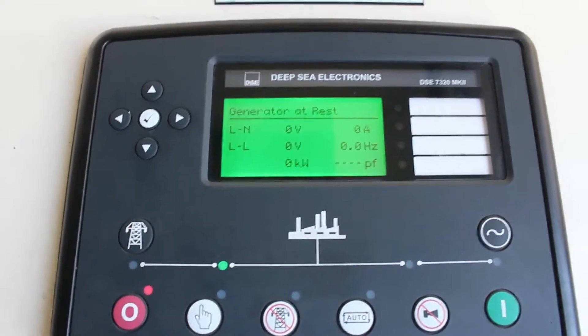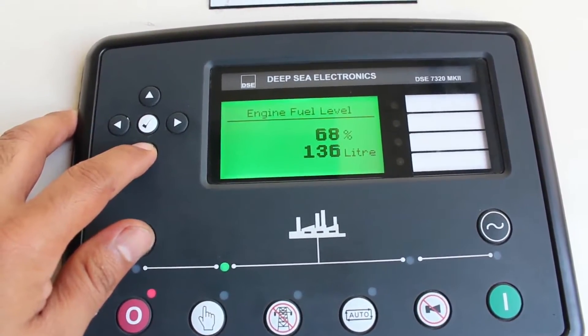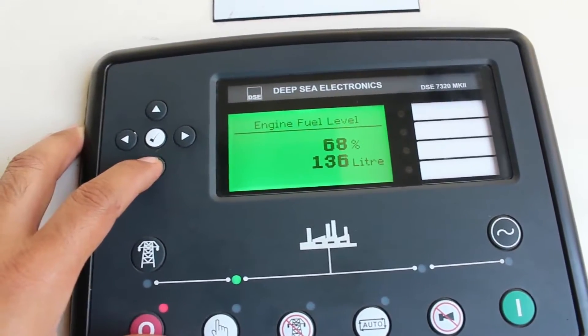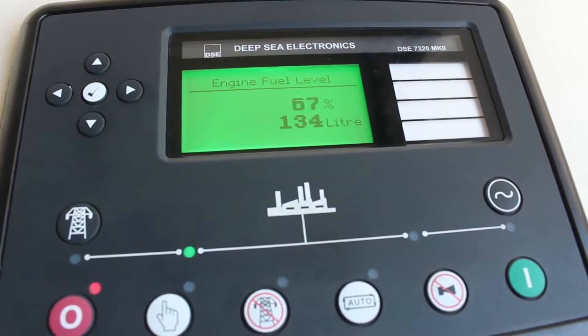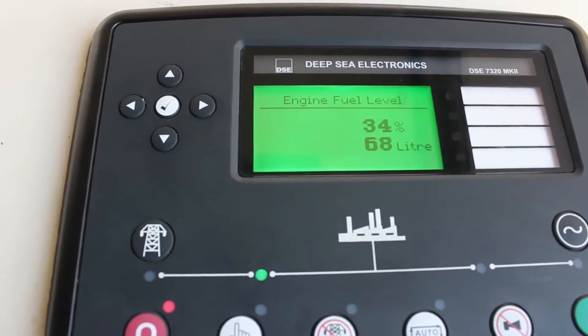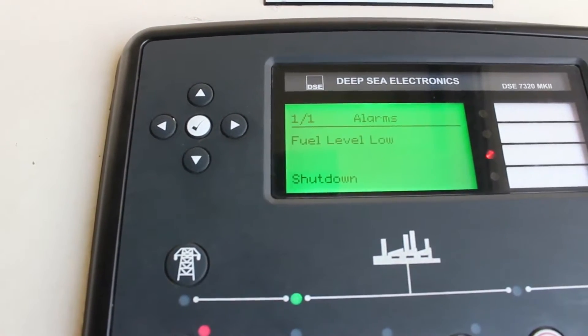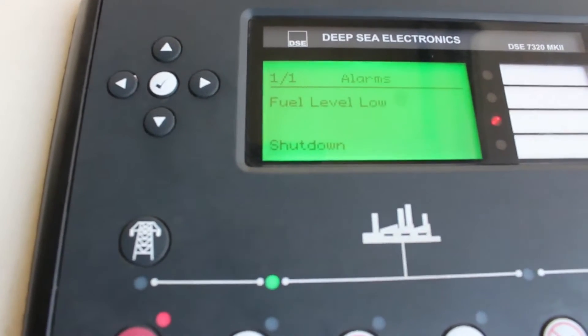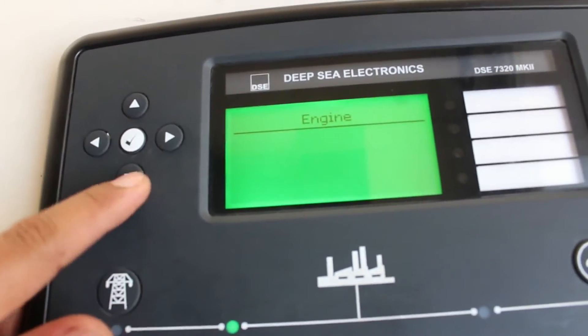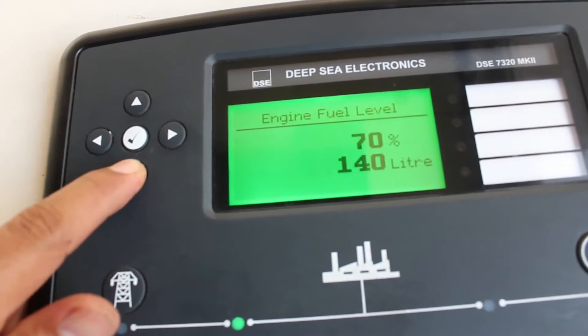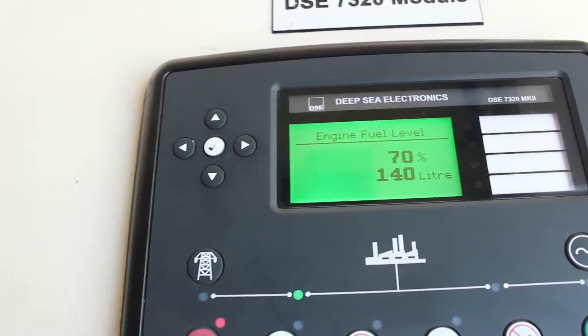Now this is our module. I will go to the engine to check. The fuel is at 68%, meaning you have fuel. For example, I will move the fuel gauge to make it zero. If I move it, it also moves the percentage of your fuel. I press it up and this becomes 'fuel low'. I put it back because my fuel is not full, so now it reads back again. I reset the alarm and go back to the engine — you have 70%, so now you can see the percentage usage of your tank.